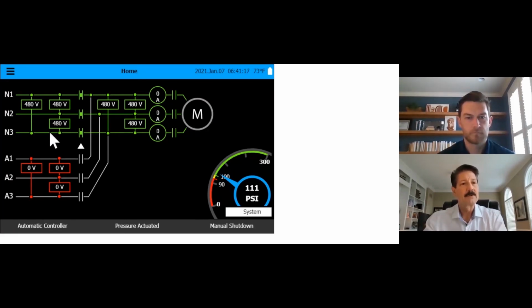Now below this is quite nice because what we're showing here, if we did have an automatic transfer switch added into this with a genset, this is what you would see below it. You see A1, 2, and 3, alternate power, phase 1, 2, 3. In this particular case, the genset itself is not running because we have red being off or stop, 0 volts in each of the boxes across the phases.